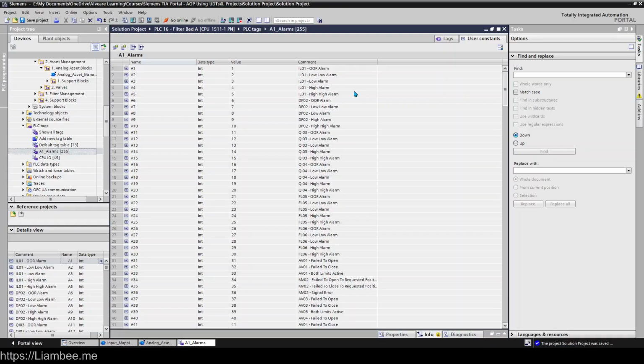It doesn't have to be, but if you make it as a function block, you're going to have to reinitialize parts of your code in order to service a new alarm. Having it as a function might just make that a bit easier, but it depends how you want to manage your actual alarm, which we'll come on to later on in this section.